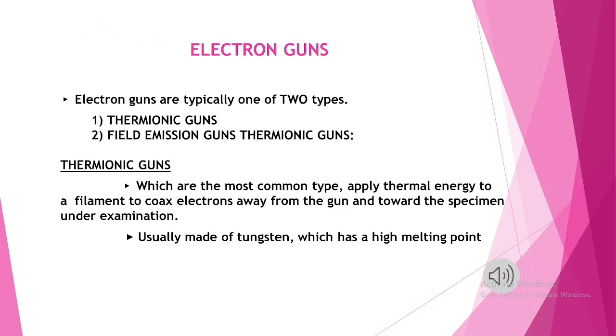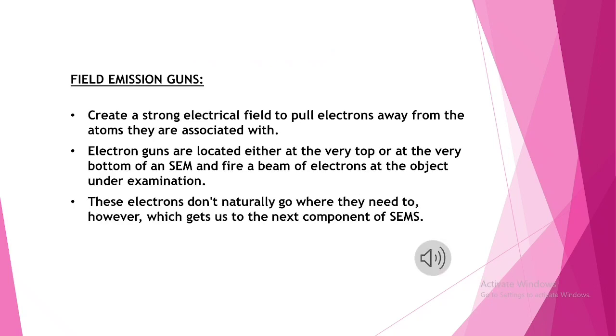The electron gun is one of the major parts of a SEM. It is mainly classified into thermionic emission and field emission. In thermionic emission, the metal is heated to a sufficient temperature to enable free electrons to come out of its surface. In field emission, a very strong electric field is applied to the metal, which pulls the electrons out of the surface due to the attraction of the positive field.